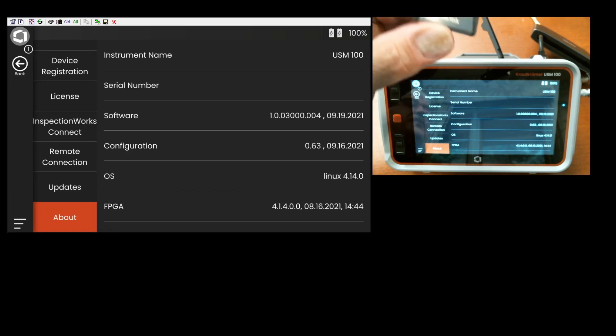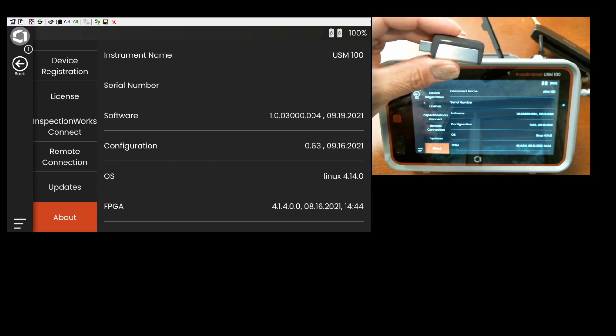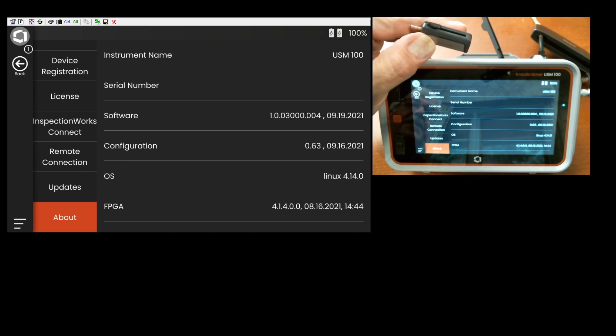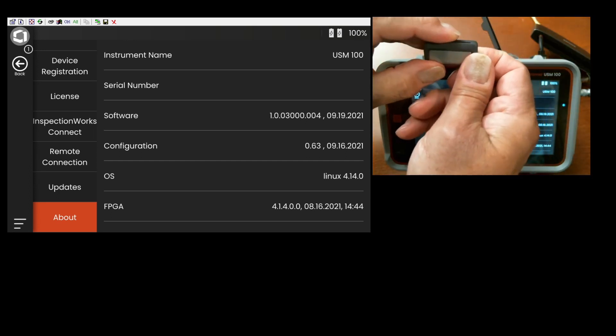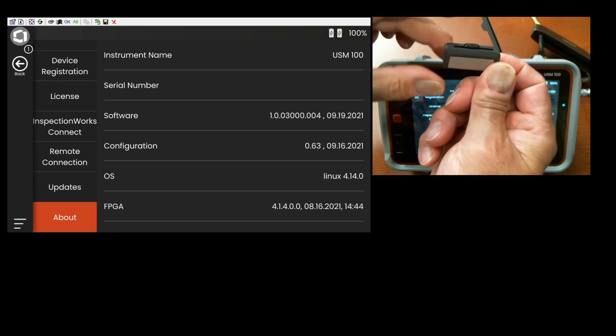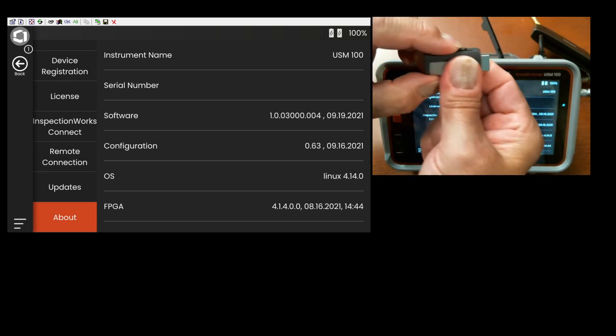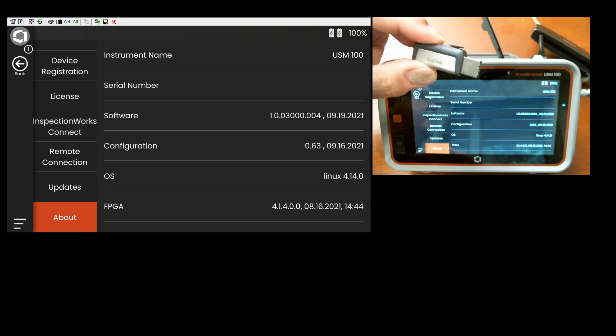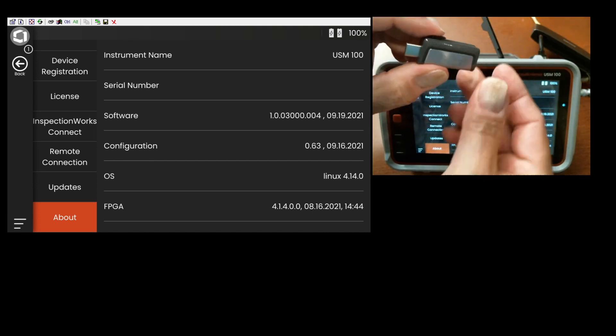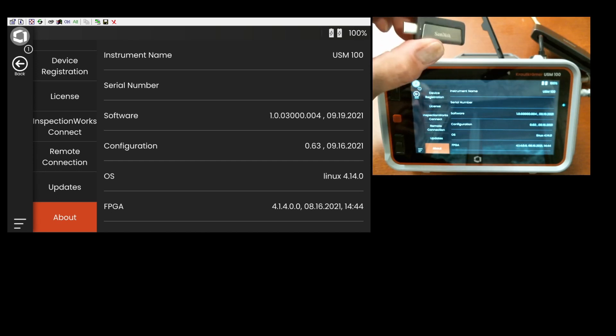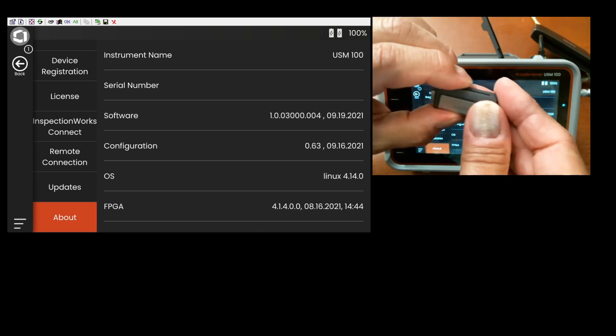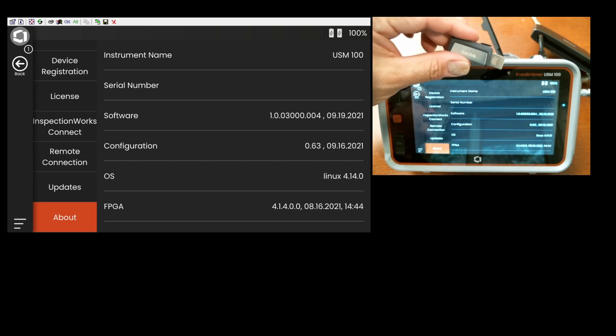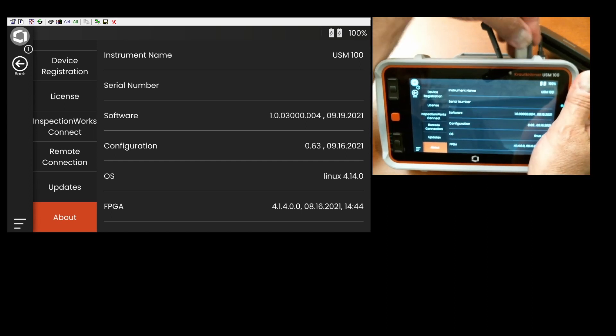Switching back to our instrument now. I'm using the USB stick that comes with the instrument. This USB stick has a little slider on the side. With the slider in the center, the USB ports are not exposed at all. Slid one way and latched, you get the traditional USB style connector. Push down, pull it the other direction, there's a USB-C style connector. You can use either one of those on the instrument. On my instrument right now, I have my docking station plugged into the USB-C. So we're going to use the older style USB connector. We'll go ahead and insert that into the instrument.